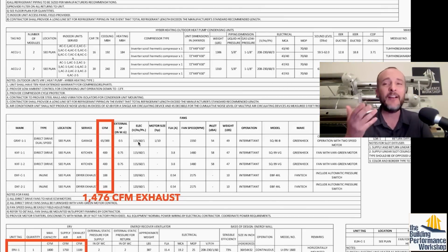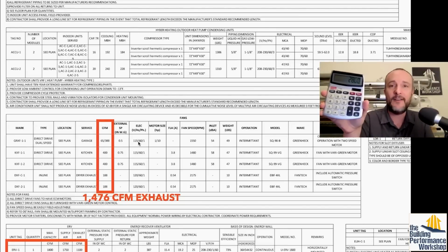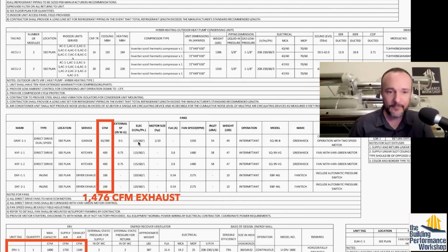50. Now in a very, very big home that's shaped like this one is, it's pretty easy to get really low ACH 50. If you test a Walmart, it's always going to pass the ACH 50 test because it's just so big and fat. There's no other reason. It's not that they did a good job air sealing it. It's just the fact that they're taking advantage of this giant fat airspace inside of it. So in a home like this, that's more barrel shaped, you're going to have the same ability. So let's assume that we're going to be able to hit 2,800 on the CFM 50 for the blower door. We might even do better than that.